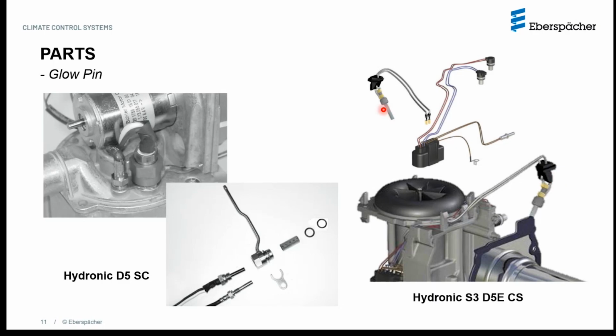Once again, glow pins are built solid, which means the chances of failure are very, very low. So unless you have a justifiable reason, or through the activation of fault codes you know you have a bad glow pin, you would not have to replace it. You'll have to unpin the glow pin from the lead harness assembly, which has the two sensors, the inlet and the outlet sensor, and also the flame sensor and the ground cable for the ECU. All of this is pre-assembled into the connector. So all you would have to do is unpin it, and if you're replacing it, of course, push the new glow pin back into the connector.